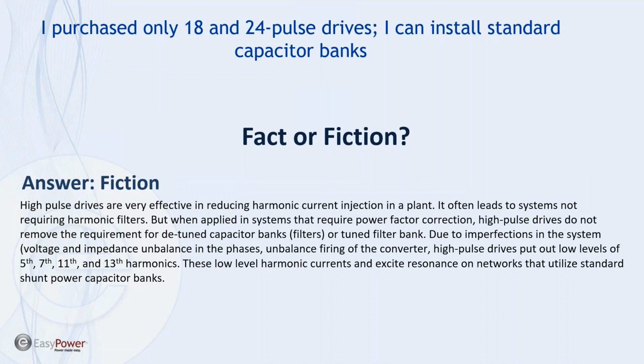18 and 24 pulse drives will put out 5th and 7th harmonics. Yes, under ideal conditions in a laboratory, 18 and 24 pulse drives do not put out harmonics, but the reality is that the fundamental voltage is not perfectly balanced. The impedances of the network between A, B, and C phase are not perfectly balanced, and the electronics within the drive itself are not perfectly balanced.